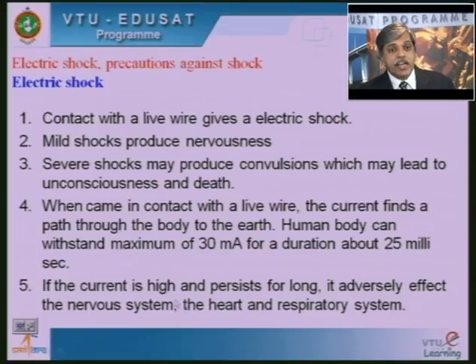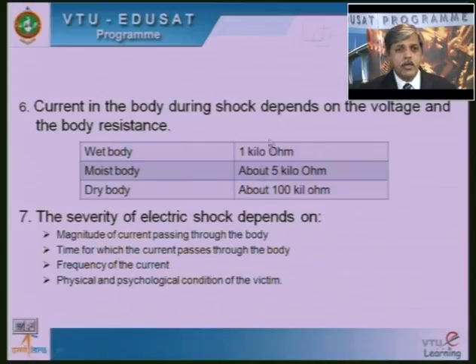If the current is high and persists for a long time, it adversely affects the nervous system. The nervous system is getting affected, therefore the heart and respiratory system, which also depend upon the nervous system, will get affected. So this may cause severe damage to a person who got a shock. Current in the body during shock depends on the voltage and the body resistance. If I have a wet body, my resistance will be up to 1 kilo ohm. A moist body is about 5 kilo ohms. A dry body is about 100 kilo ohms.